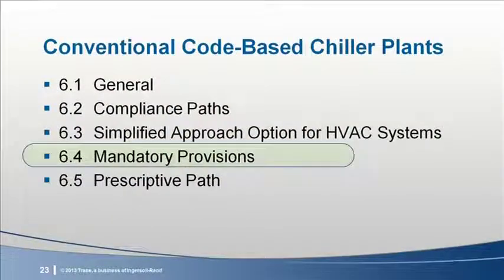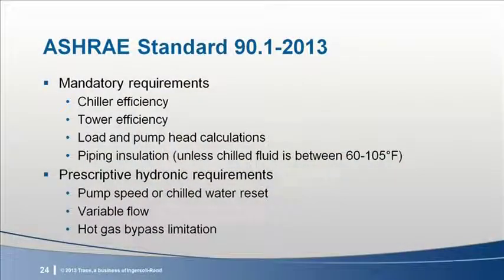Let's turn to 90.1/2013's mandatory provisions, section 6.4. In the mandatory requirements, we have the first hurdle, equipment efficiency requirements. For centrifugal chillers, these requirements are modified for non-standard chilled water leaving and condenser leaving temperatures. For all other chillers, these are non-changing requirements calculated at AHRI standard test conditions, even if the chiller is applied at non-standard temperatures. There are scope limits for temperature that apply to all types of chillers. If a chiller is outside of the scope, then there is no minimum efficiency requirement and the chiller may be used without restriction.